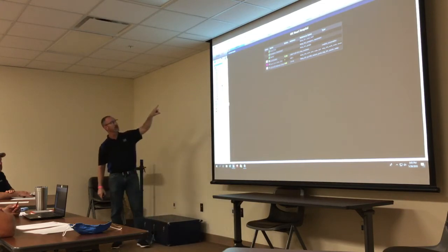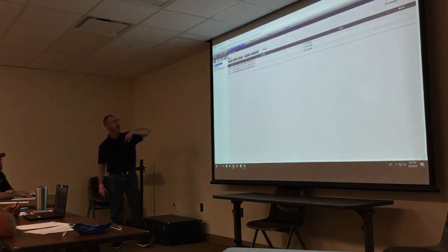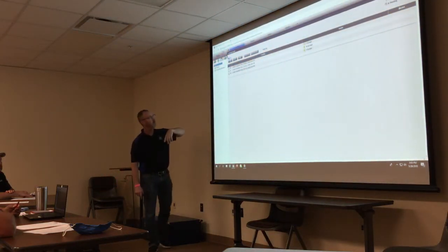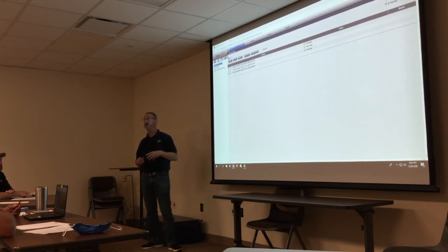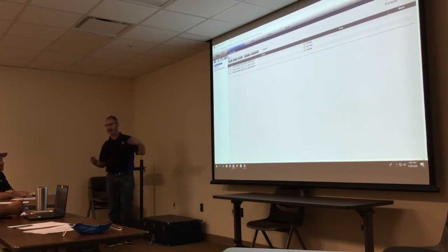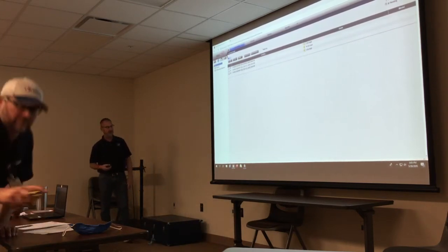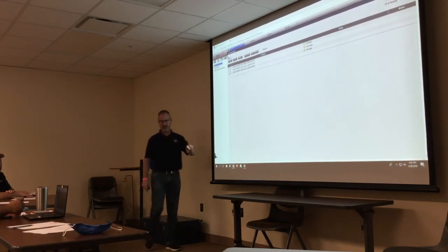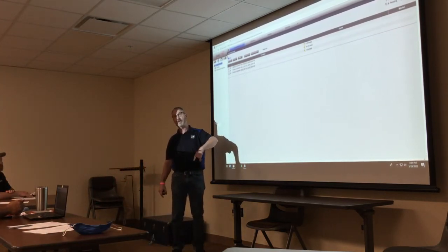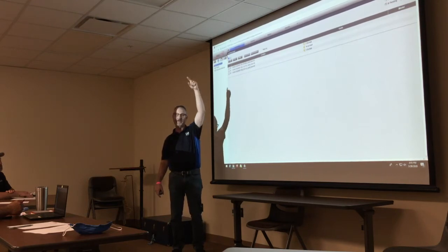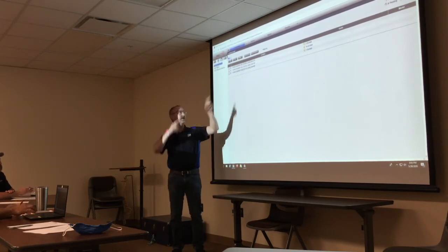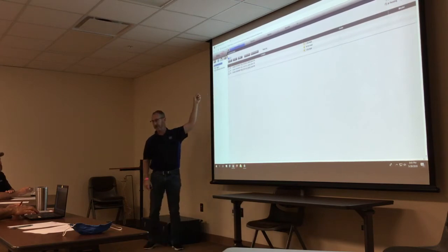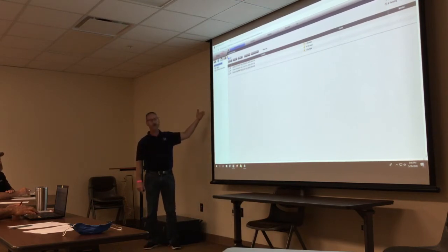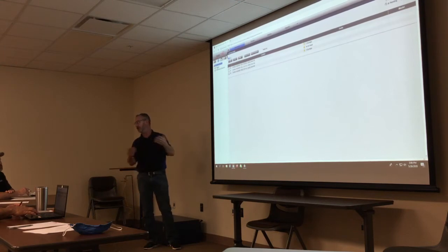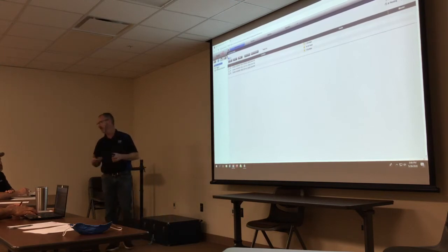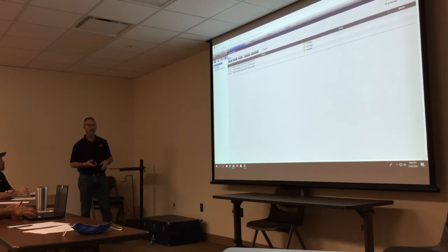The next tree over, it looks like a bunch of monitors - that's the network tree. It represents how I physically wired the controllers together throughout the building. For example, if I started on the first floor VAV1 and went up to the second, third, and fourth floor with a wire, that's how it has to look in this network tree. But the other tree represents how it actually exists in the building.